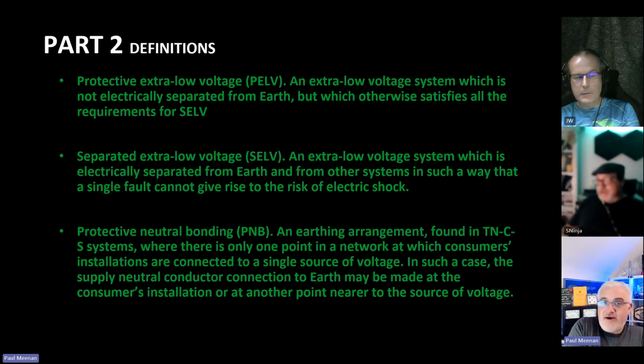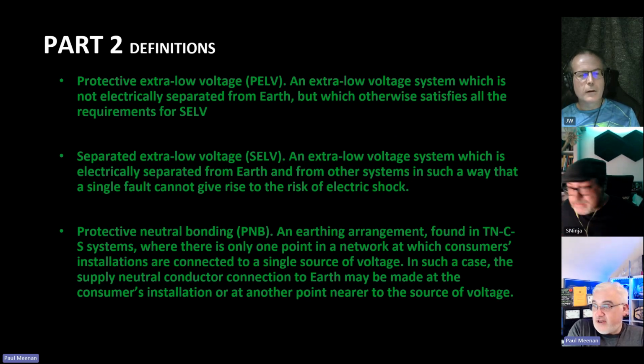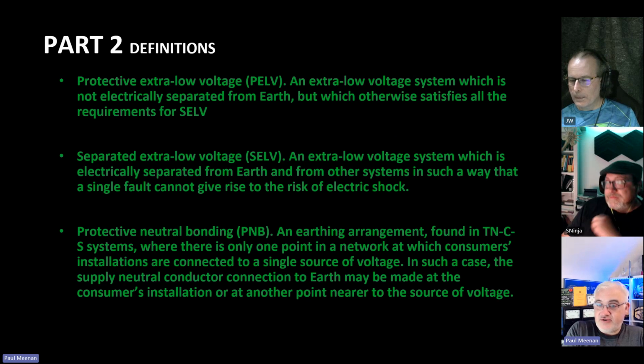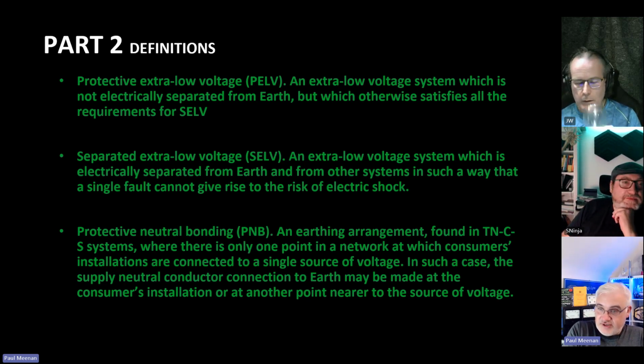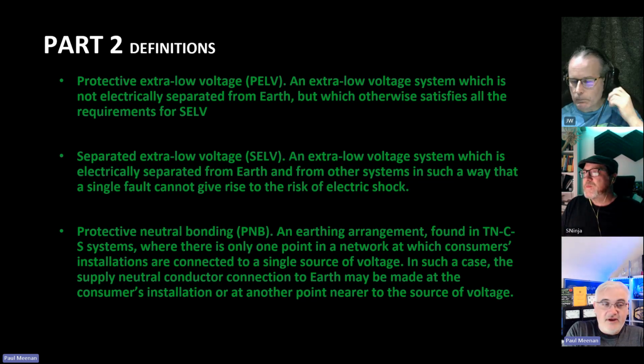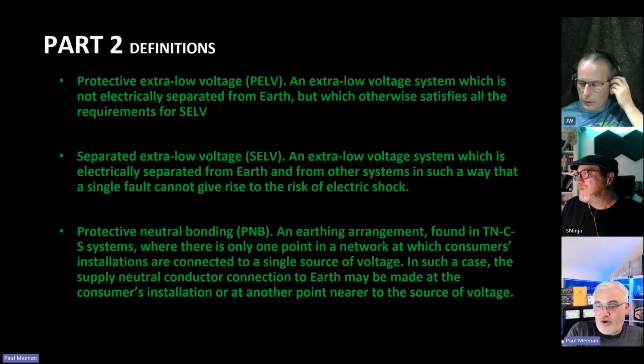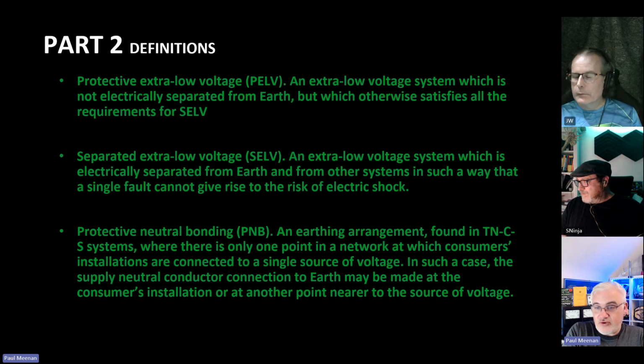Back on PNB - a certain station on the DLR has its own DNO transformer, and right next to the transformer on the other side of the wall, I know because I basically worked on it, there is a massive solid copper link between the neutral and earth, and that station is a PNB. I know, I witnessed it being done.